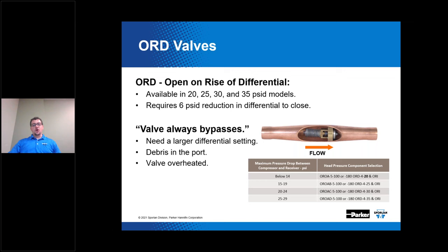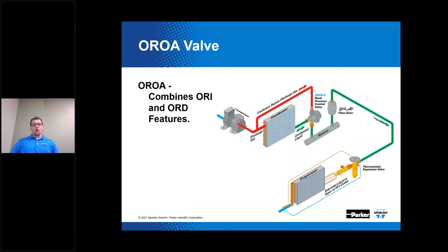The OROA is a single valve version of head pressure control designed to stack liquid in the condenser and bypass hot gas to the receiver. It's essentially a combination of the separate ORI and ORD valves. When you desire to use only one valve, you can consider the OROA. This valve responds to your outlet or receiver pressure — OROA stands for Open on Rise of Outlet pressure, in this case receiver pressure.